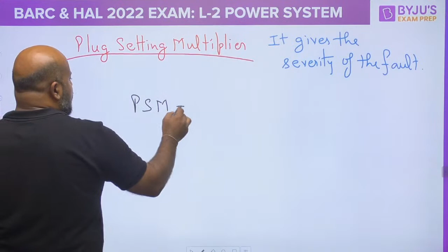Plug setting multiplier is a parameter, a criterion, which tells us the severity of the fault, how dangerous the fault is. This information is given by the plug setting multiplier. So we can say it gives the severity of the fault. So how are you going to find this value, this parameter?